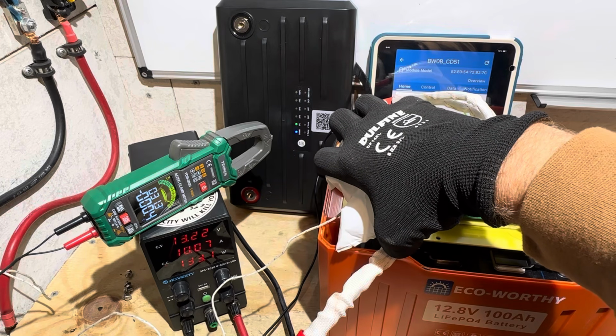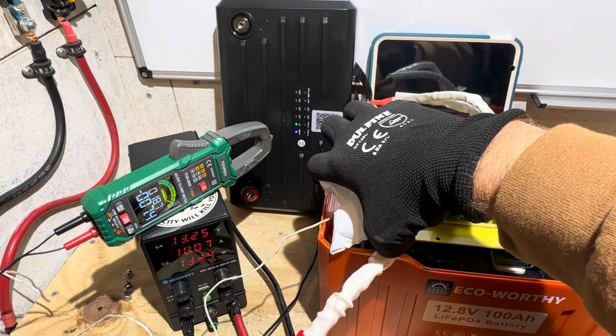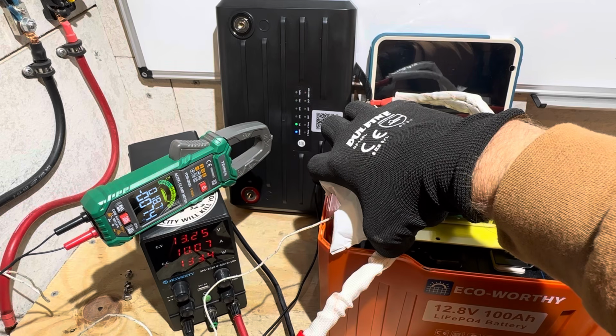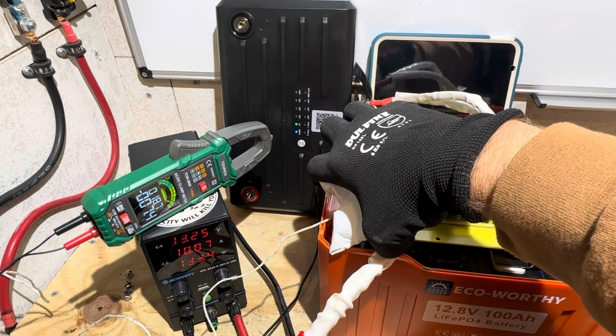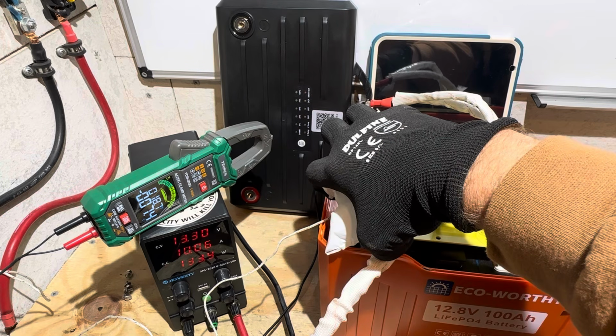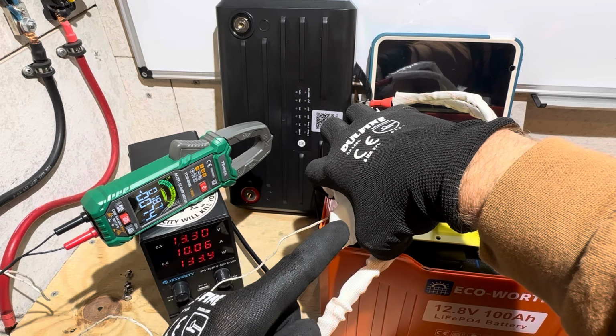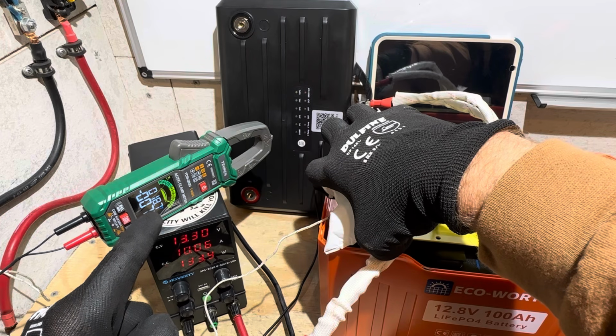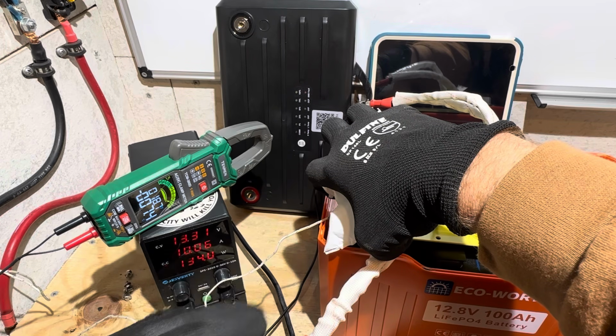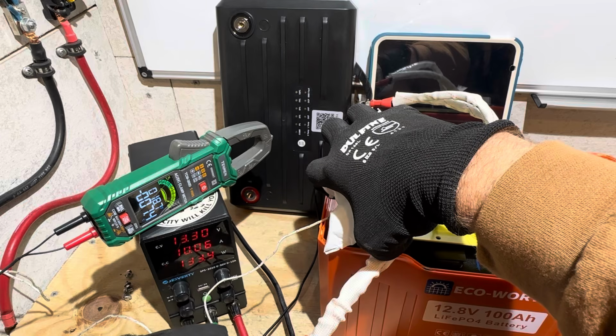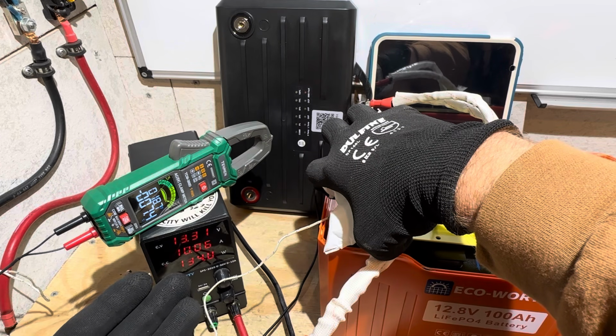Alright, we're below freezing, below the 19 degree Fahrenheit mark they had in the book. Remember, they had a plus or minus 9 on their trigger point. That's 2 minutes with the ice pack applied, around 18.7 degrees Fahrenheit and no trigger. I left it on for 2 minutes to see if there was a trigger delay, but it's not triggering low temp charge protection.